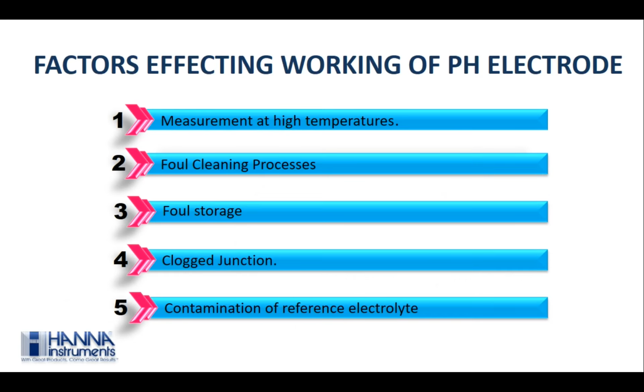The factors that affect the working of a pH electrode can be high temperature. Continuous monitoring at high temperatures can reduce the life to almost one-fourth of what is expected when operated at ambient temperature. If you are continuously using an electrode at 80 degrees or 90 degrees, you will be able to utilize the life of the electrode for only 1 month. After 1 month, the electrode will start giving errors or erratic readings that you cannot identify the exact reason for.